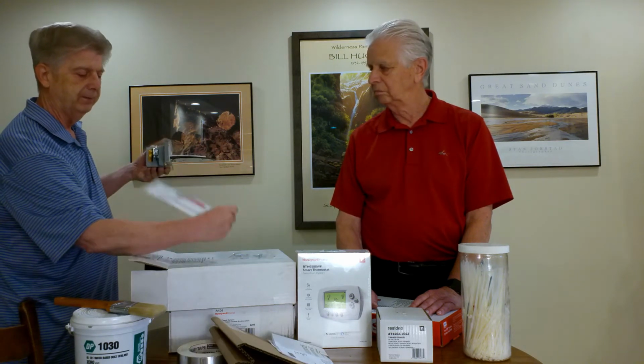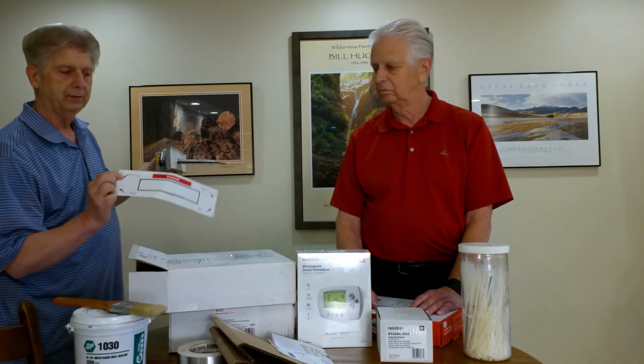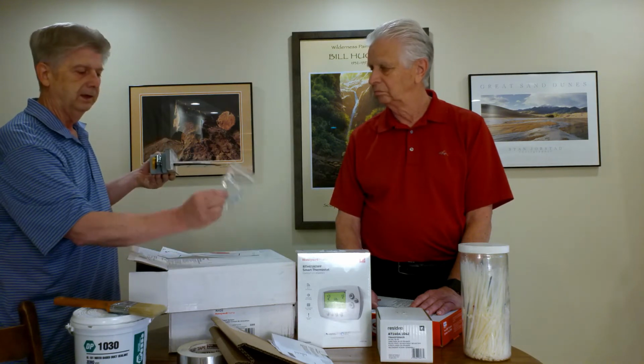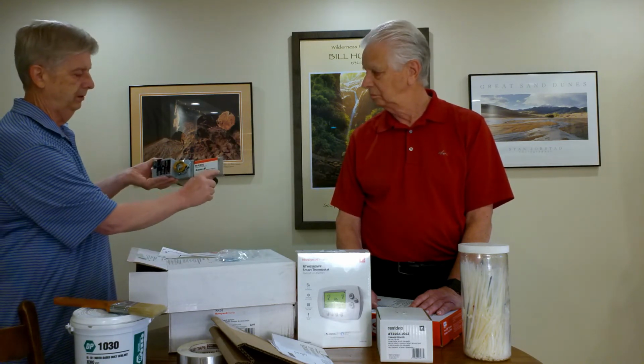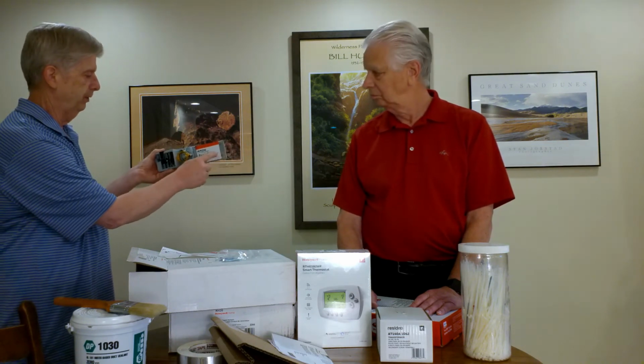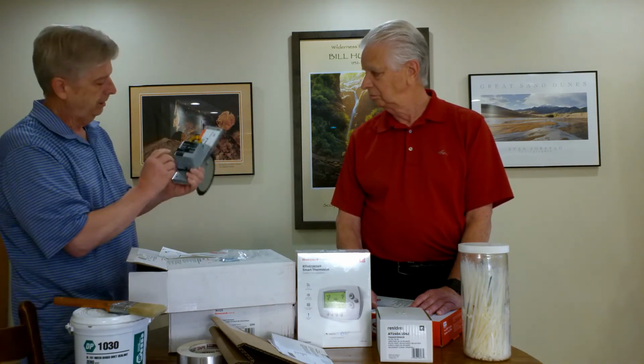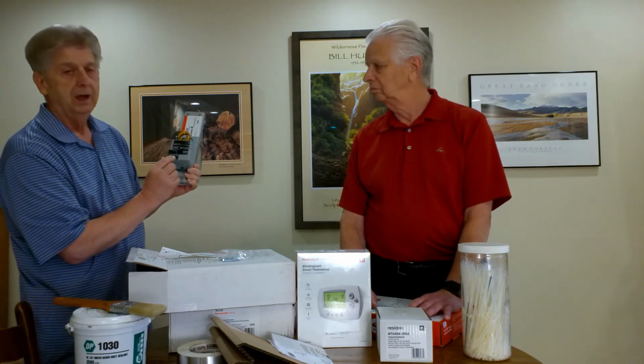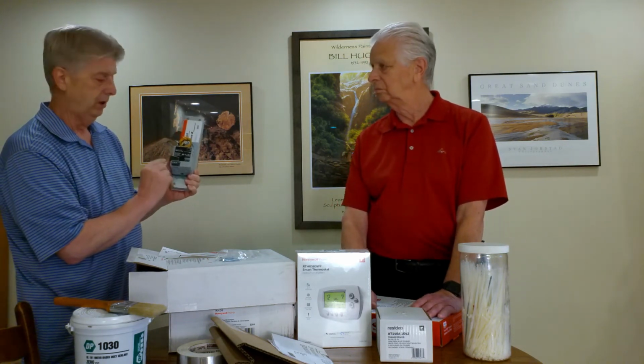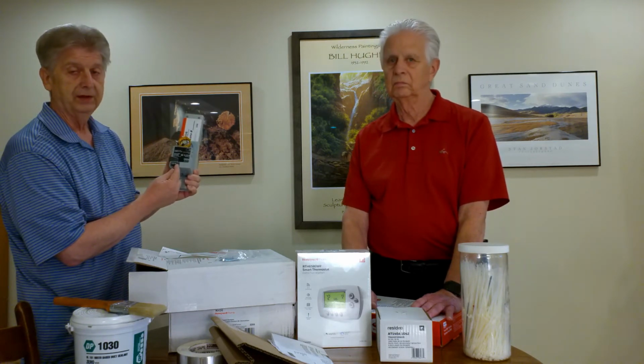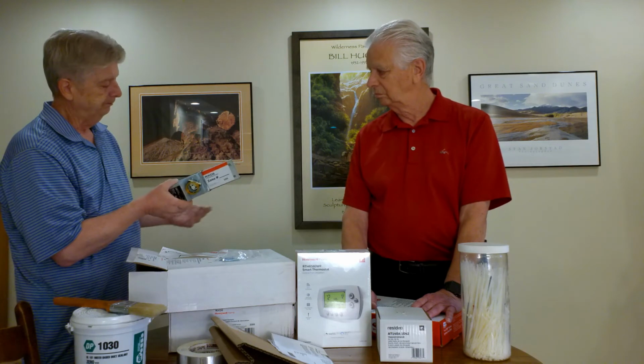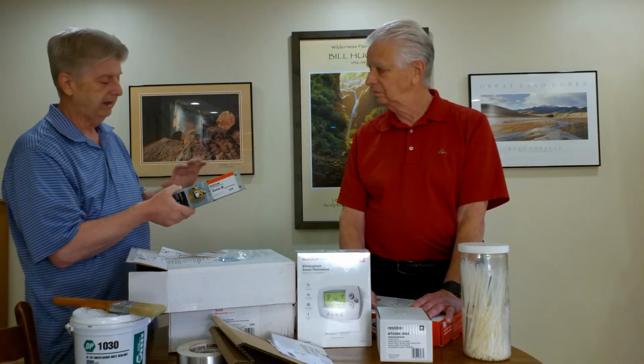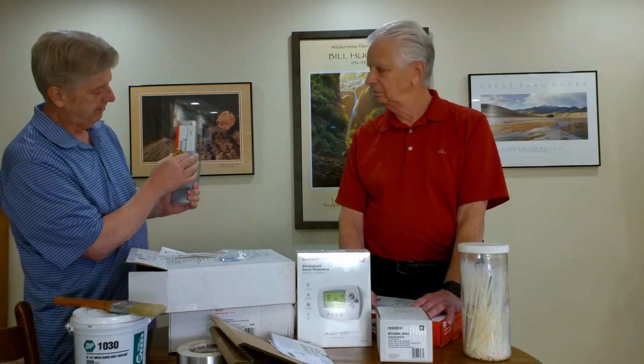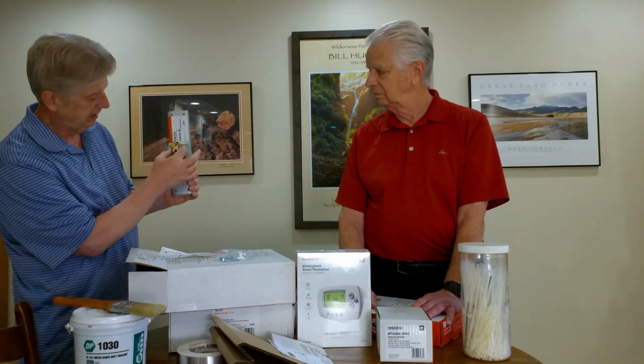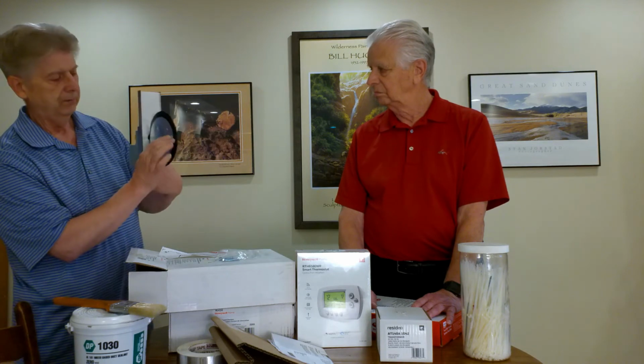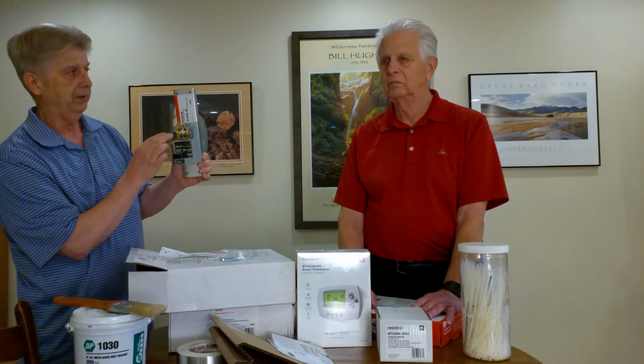Previously, while you have this up there, you'll drill 4 holes with a little drill bit to help pilot these screws in, which will go in the corners of the damper. The damper has 3 connectors so that you can power open or power close the damper. It takes about 90 seconds to run through a cycle. You have an adjustment here that you can rotate to put in line with the blades so you can see easier when they're open or closed.